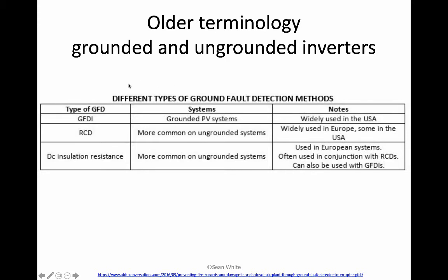The different types of way to detect ground faults. So right now what we're doing is we're looking at ungrounded systems right here. And this is called a residual current device. What this pretty much does is it will just compare positive and negative and make sure that they're equal. It's sort of like a GFCI. It just makes sure your positive and your negative is in equal current.